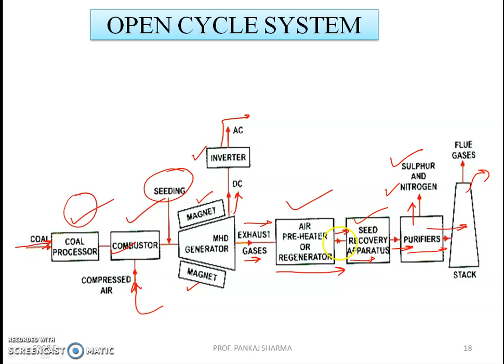In the open cycle system, to attain such high temperatures, the compressed air used to burn coal in the combustion chamber must be preheated to at least 1100 degrees centigrade. A lower preheat temperature would be adequate if the air is enriched in oxygen, in good quality or quantity, pure oxygen.